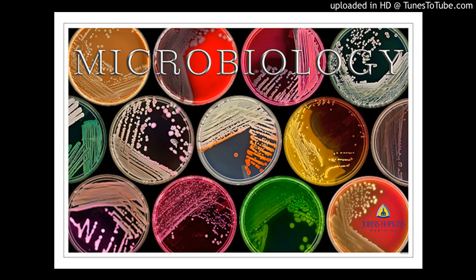Okay? One example of where this happened is where they used concentrated hydrogen peroxide to sterilize endoscopes that were used in colonoscopies. Okay? This works pretty well as long as you get all the waste off. If you don't, you leave it on and put it in this, it quickly gets inactivated and organisms can stick around. And about 2 years ago at UCLA, this happened.